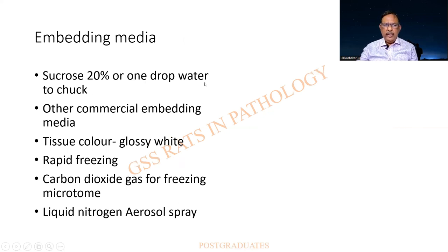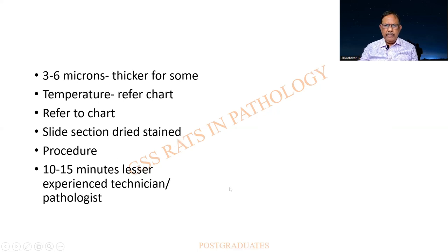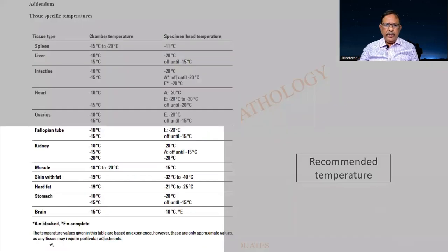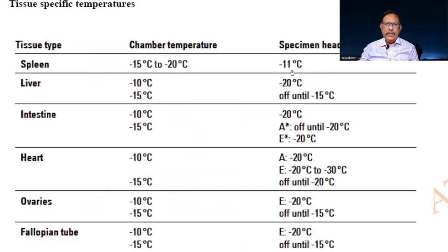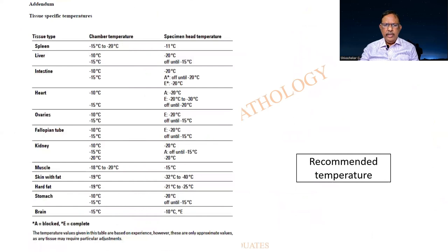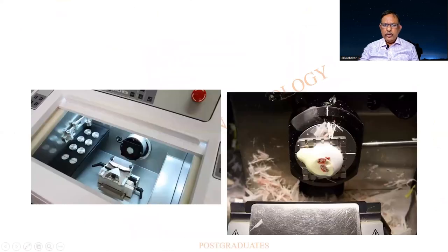The embedding media will be either a drop of water or sucrose itself — there can be other commercial embedding media which can be used, all helping in rapid freezing. Sometimes carbon dioxide snow is used for the freezing microtome, and liquid nitrogen as mentioned earlier. The time limit can be about 10 to 15 minutes, and it can be much less in the hands of an experienced technician and pathologist alike. This is a temperature chart which I would like you to commit to memory — for example, the spleen, what is the temperature? Liver, what is the temperature? Accordingly, you can give instructions for the adjustments. The recommended temperature chart is a good chart to refer to.